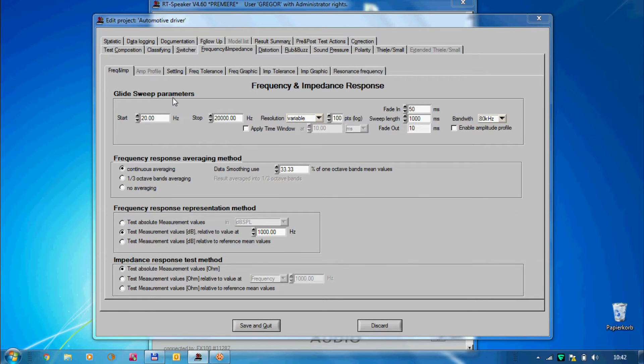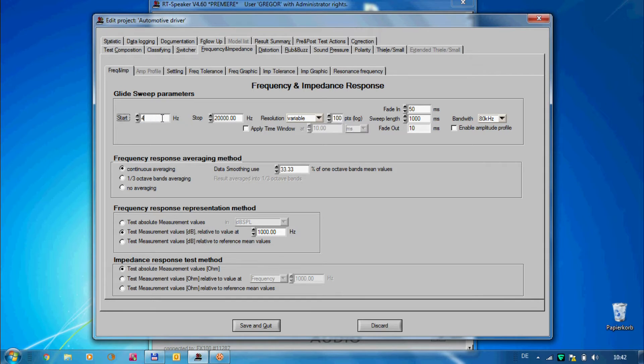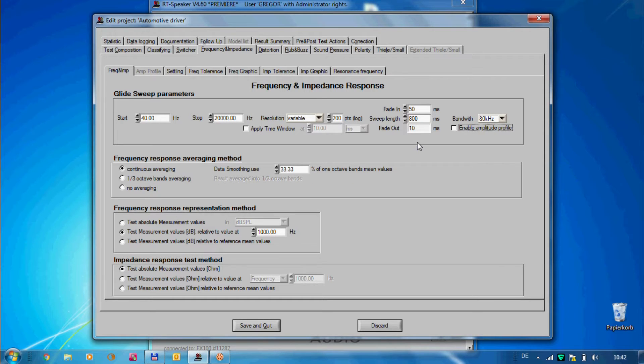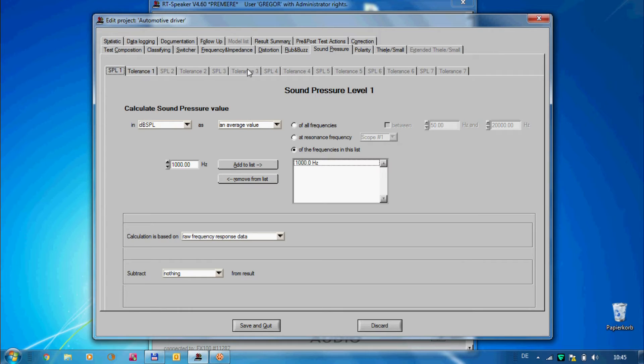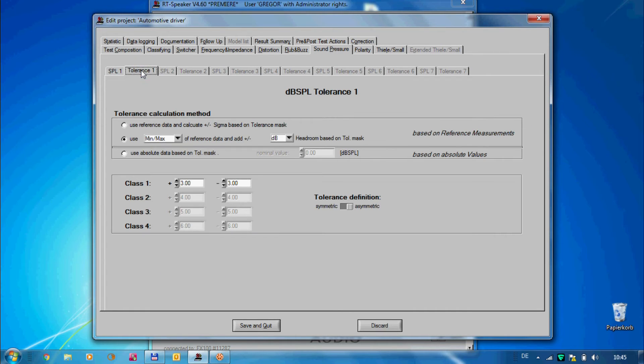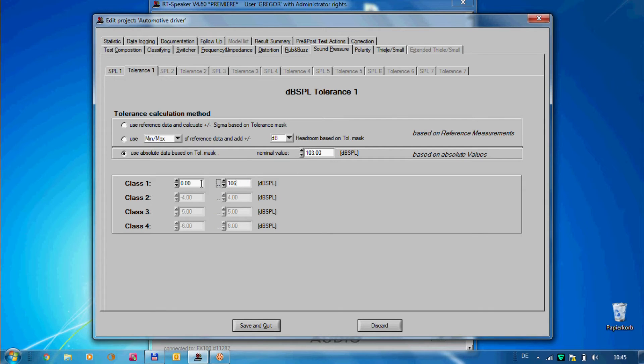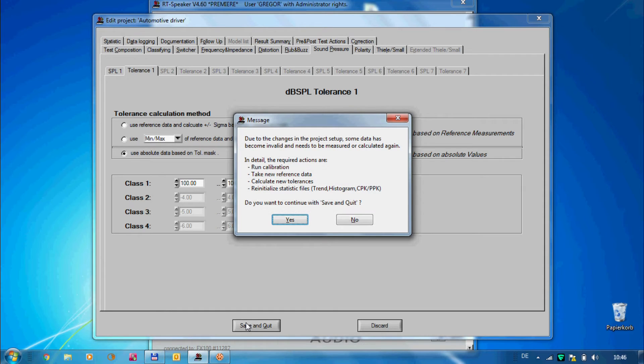We can set details such as start/stop frequencies and duration of the sweep signal. By default, pass/fail criteria are built from reference measurements. However, we can also enter absolute values when available — sensitivity is a good example for that. When leaving the configuration, the system tells us what to do next. Since this is the first time we have run this particular project, we need to run a calibration sequence.